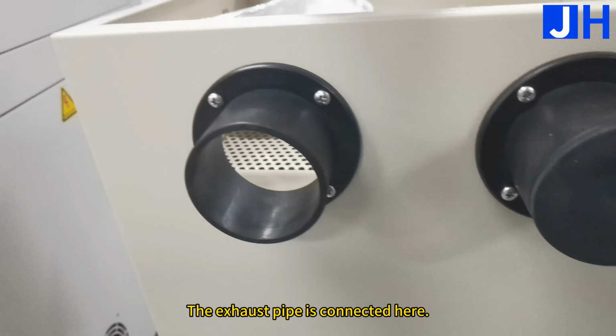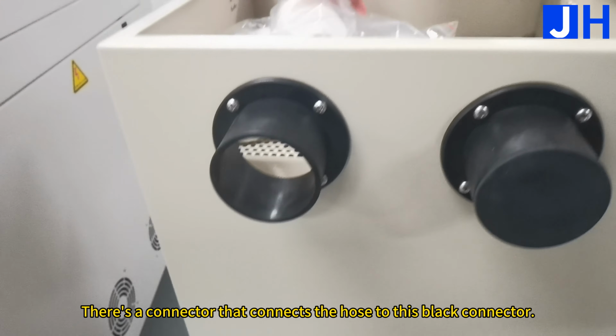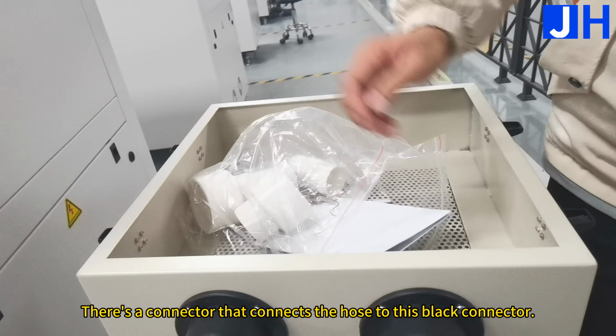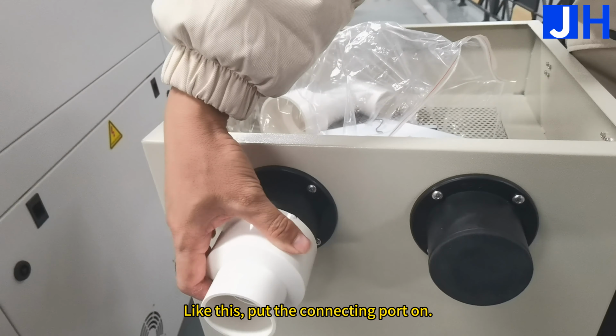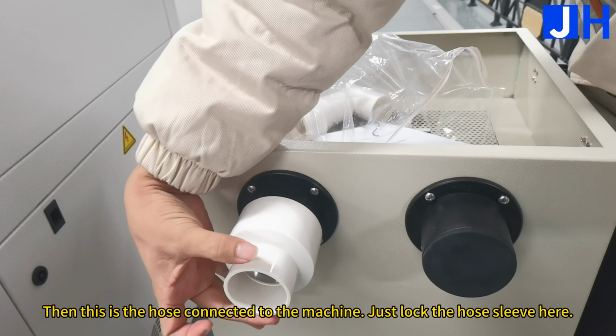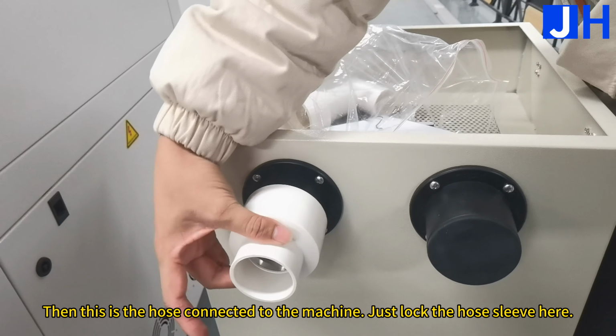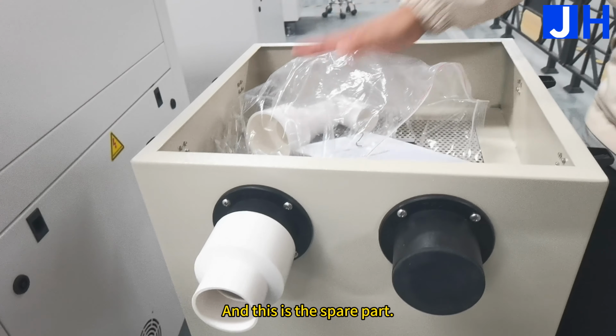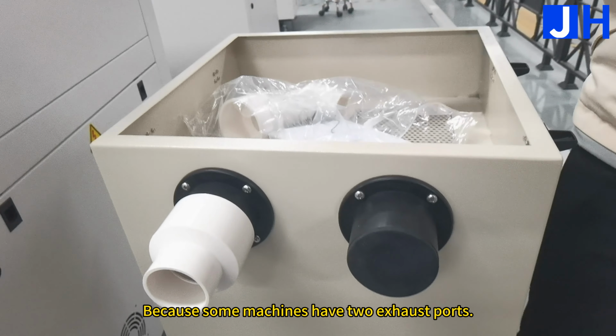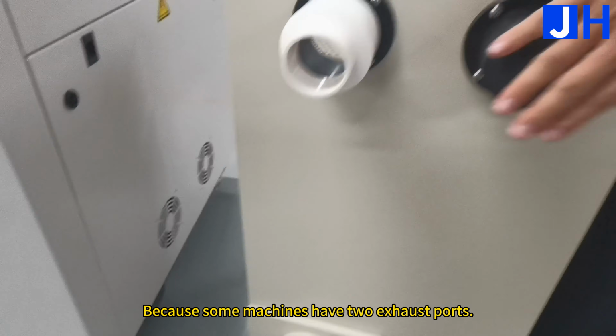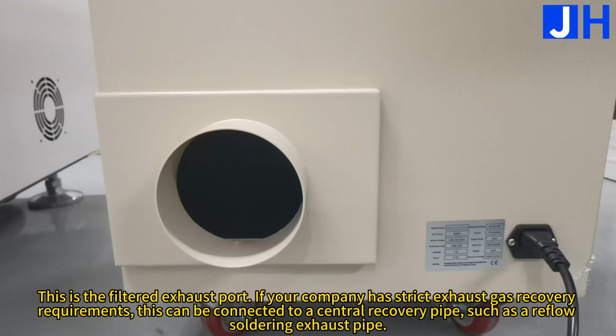The exhaust pipe is connected here. There's a connector that connects the hose to this black connector. Like this, put the connecting port on. Then this is the hose connected to the machine. Just lock the hose sleeve here. And this is the spare part, because some machines have two exhaust ports. This is the filtered exhaust port.